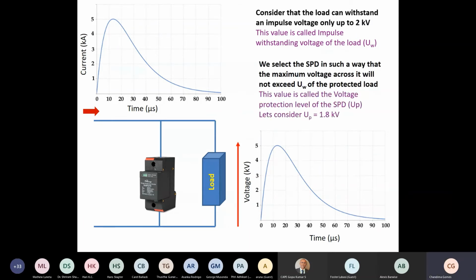say for example, we take an SPD where the UP value is 1.8 kV. That means the surge protective device will give out only 1.8 kV. So if that is the case, then my equipment is protected because it can withstand up to 2 kV. What comes out of the surge protective device is 1.8 kV. Let's see what happens now.